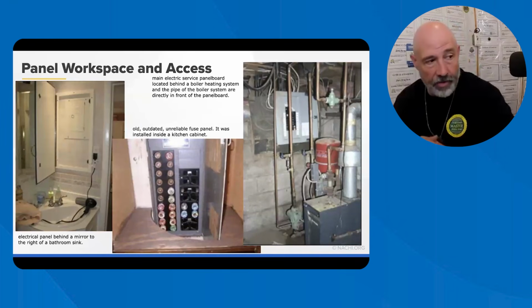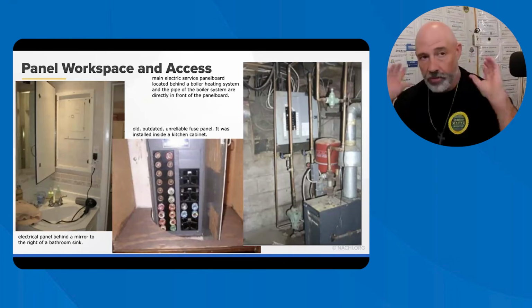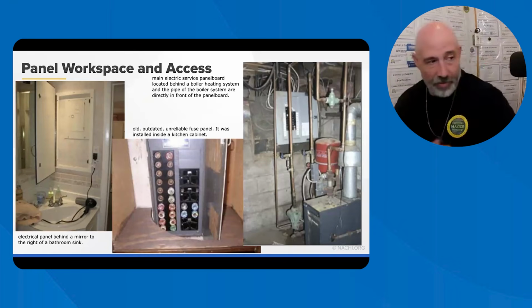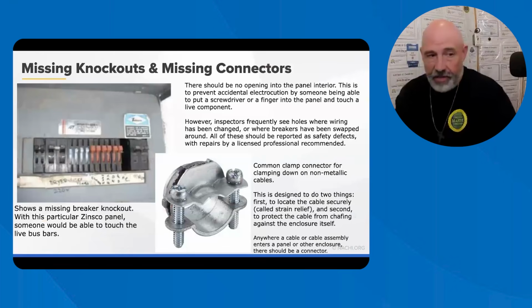Here are a couple of other weird things. One's in the bathroom. I have seen that, believe it or not. I opened up, couldn't find the electrical panel, and sure enough, it was in the bathroom. I followed the wires through the basement, and it went into the bathroom. I opened up the cabinet. There it is. I'm like, whoa. So I've actually seen similar to that one. So pretty funny. If you can't get to it, that's a really bad thing. So call that stuff out. Make sure that you're doing due diligence on this stuff because it can be problematic.